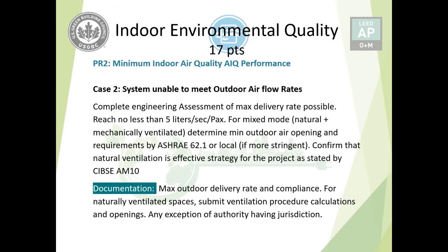Case 2 is when the ventilation system is unable to meet the outdoor airflow rates of Case 1 (8 to 10 liters per second per person). In that case, an engineering assessment must be performed to reach the maximum delivery rate possible with the installed system, and it must not be less than 5 liters per second per person. For mixed-mode systems, minimum outdoor air opening requirements per ASHRAE 62.1 apply, and whichever standard is more stringent prevails.